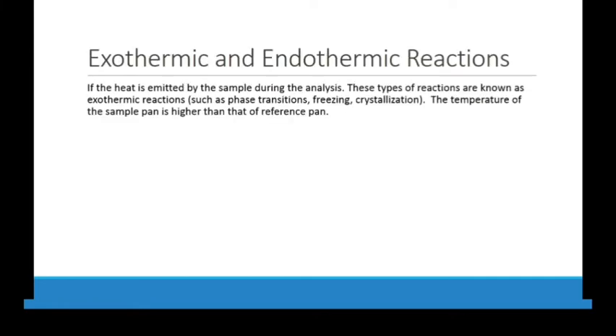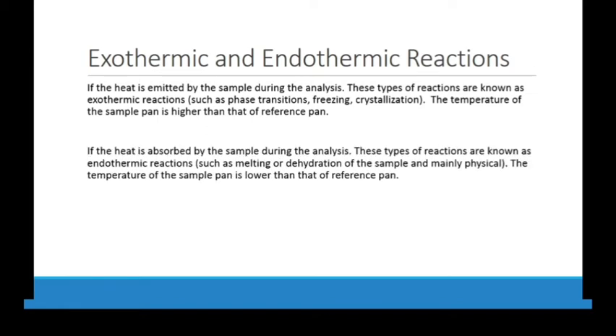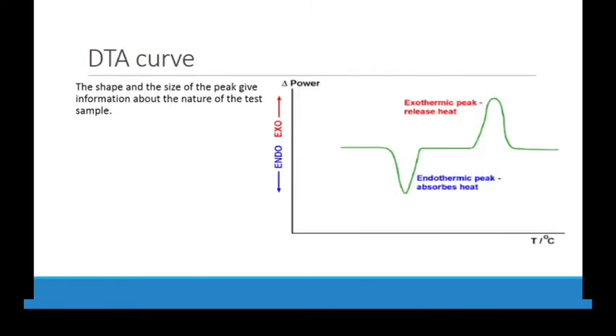If heat is emitted by the sample during analysis, these reactions are known as exothermic reactions — such as phase transition, freezing, and crystallization. The temperature of the sample pan is higher than that of the reference pan because the sample is emitting heat. If heat is absorbed by the sample during analysis, these are known as endothermic reactions — such as melting or dehydration — and the temperature of the sample pan is lower than that of the reference pan because it is absorbing heat from the surroundings and from the heater.